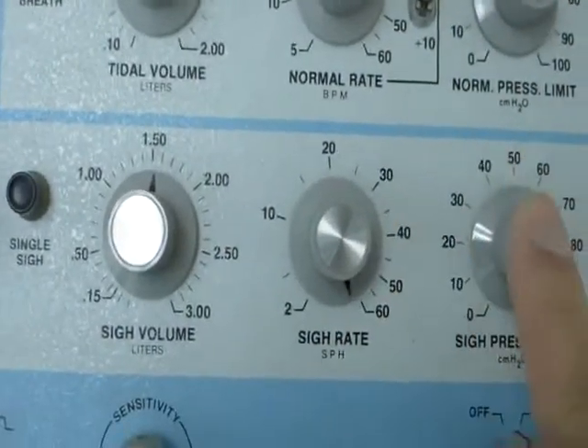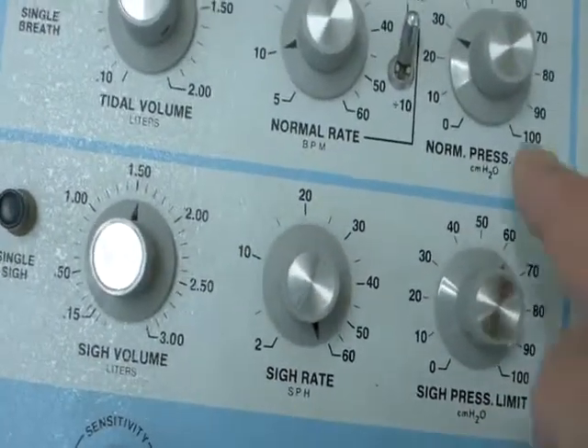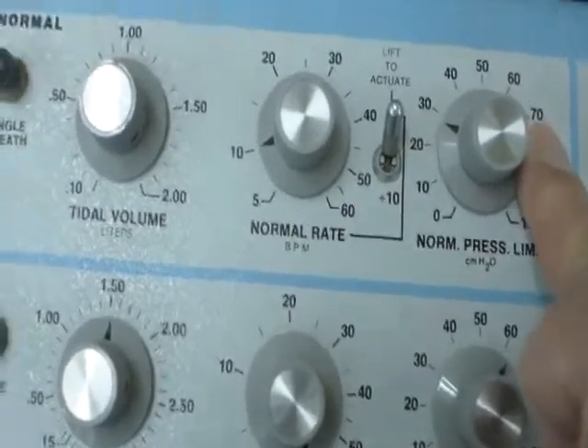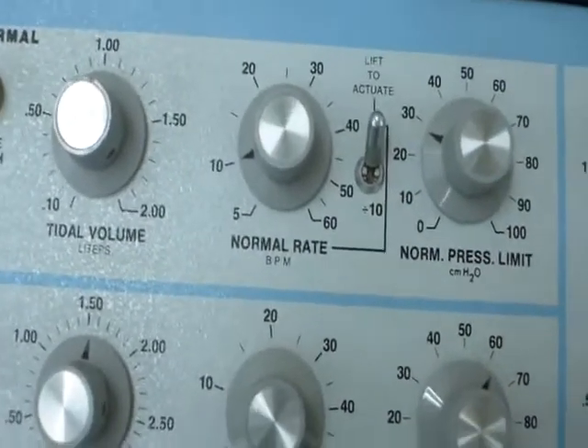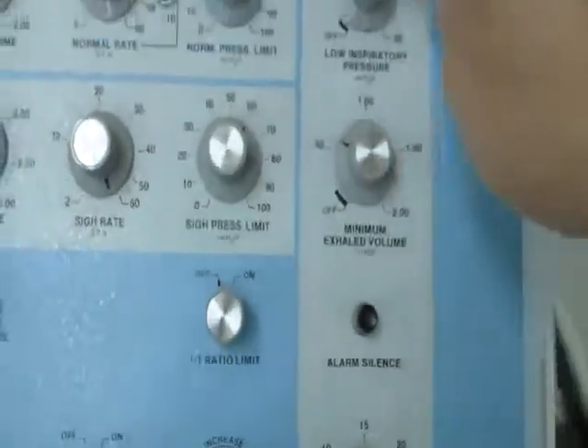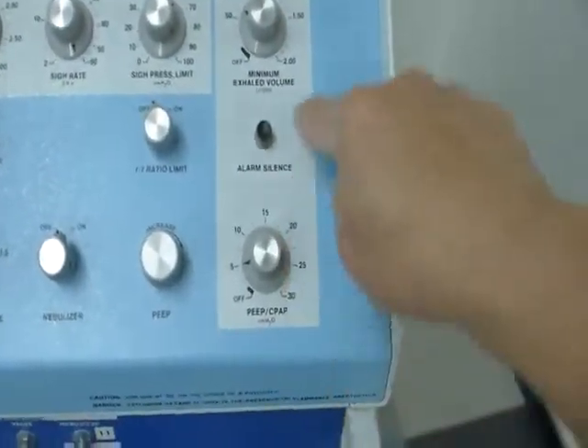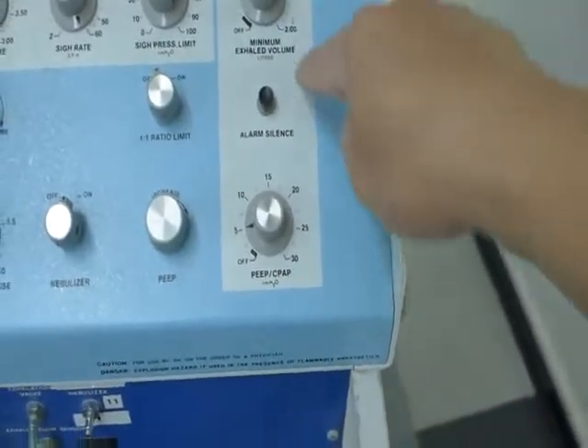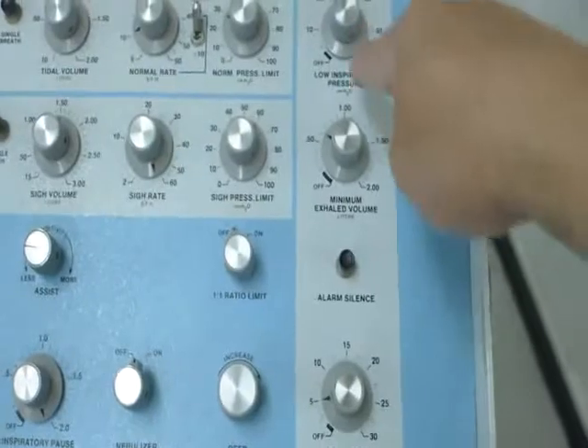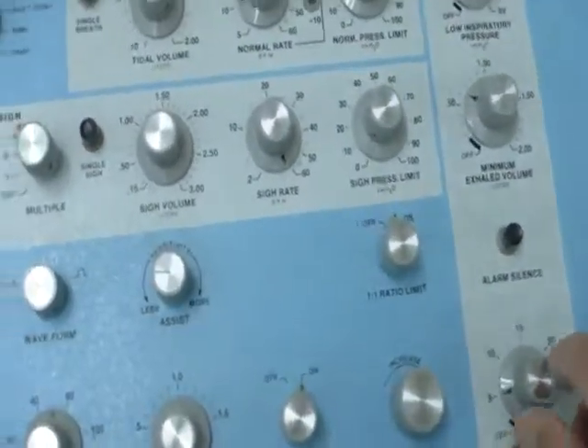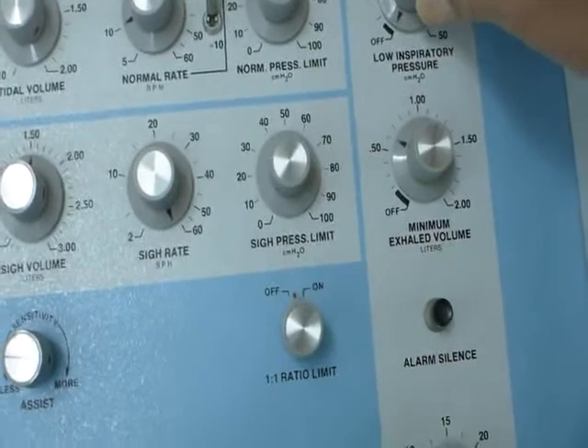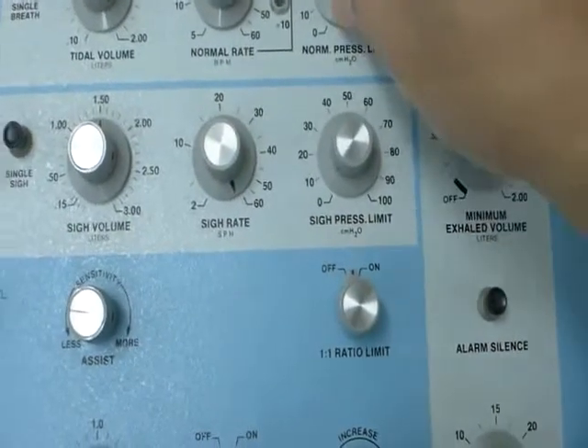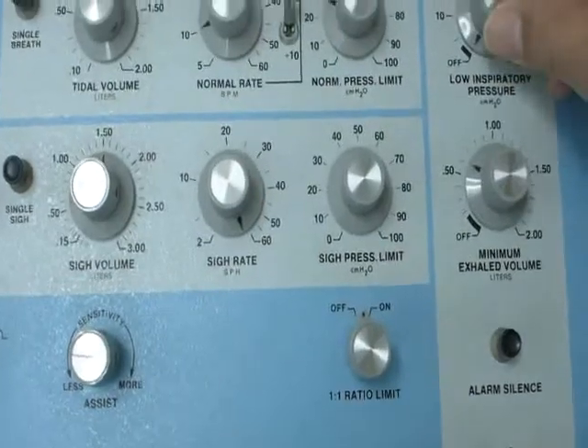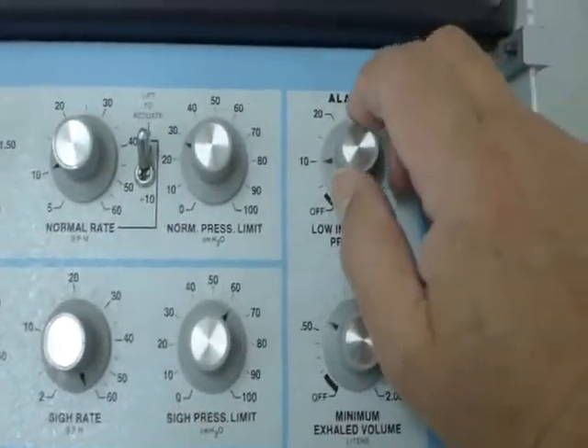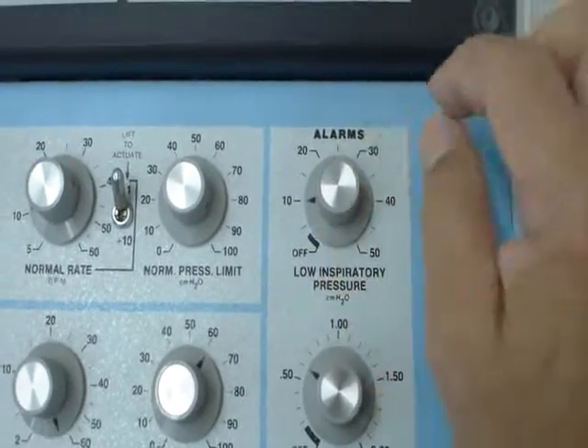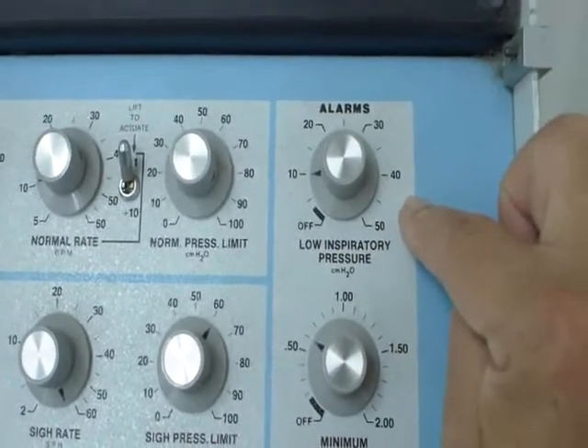Okay, and then after the over-pressure limit, we have the alarm. Actually, this one is part of the alarm. This column here is the alarm settings. All right, so we can set the low inspiratory alarm. When we have the low alarm limit, we want to make sure that the pressure we give to the patient does not drop below certain points.